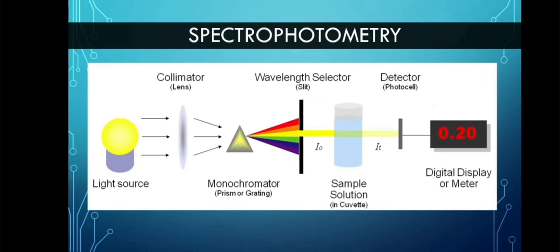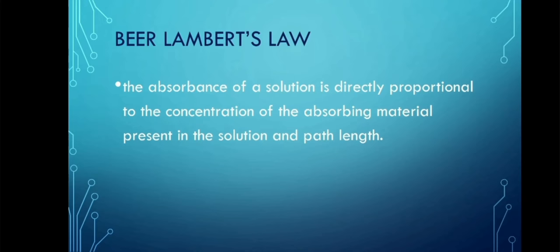Spectrophotometry consists of a light source, collimator, monochromator, a wavelength selector, sample solution detector, and a digital display or meter. From the light source, light is emitted through the collimator, then the monochromator or prism bounces back lights with different wavelengths, then it goes through the sample. The detector or photocell detects what is in the sample and the output is displayed. This is based on Beer-Lambert's law: the absorbance of a solution is directly proportional to the concentration of the absorbing material and path length.